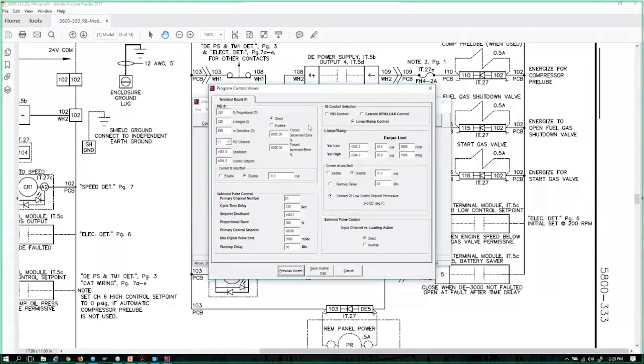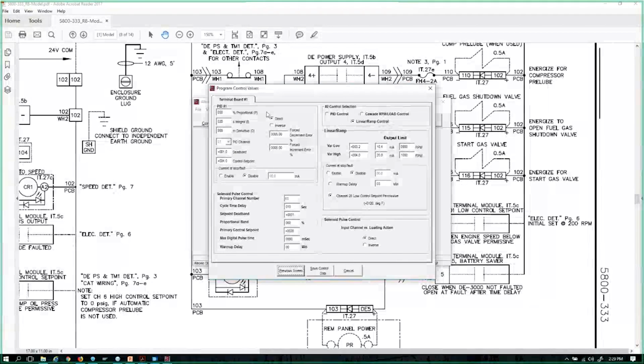The two biggest things are analog output 1 and analog output 2. Again, these can be referred to as PID loop 1 and 2, loop 1 and 2, or analog 1 and 2. So just understand there's lots of different terminology, and I think we're using at least 3 of them within the software and in our drawing designs. So let's talk about PID loop number 1 first. On the 3000, it's a little bit different, I'm finding out these days, from some of the other terminology out there on the market, but proportional, integral, and derivative still mean this exact same thing.